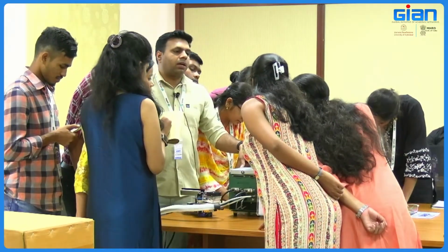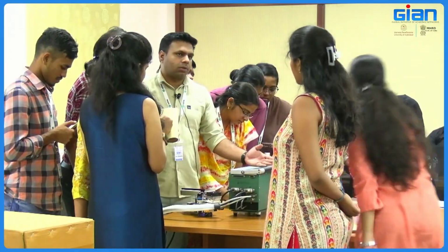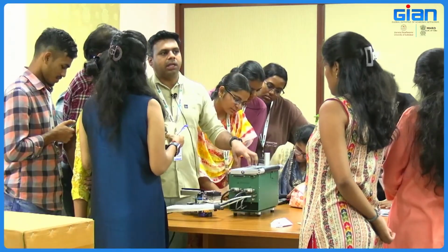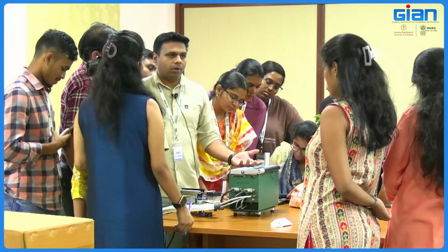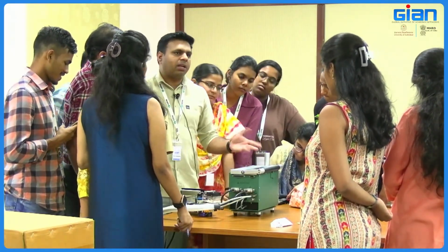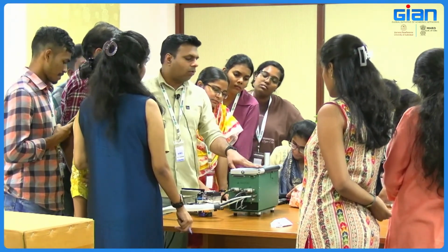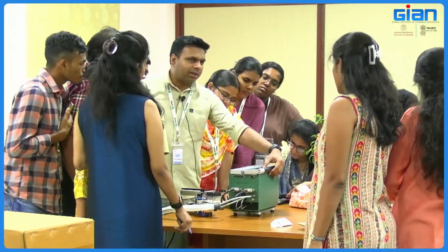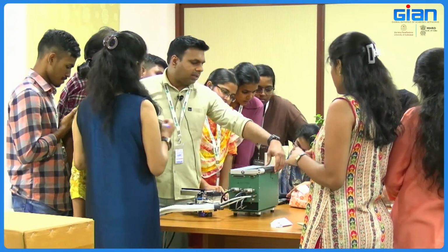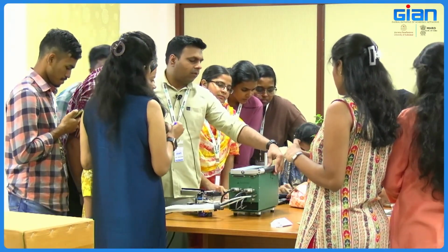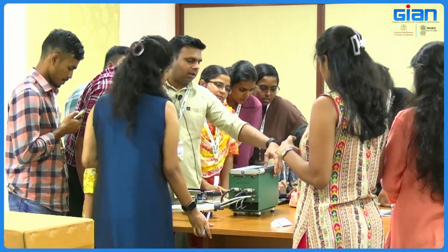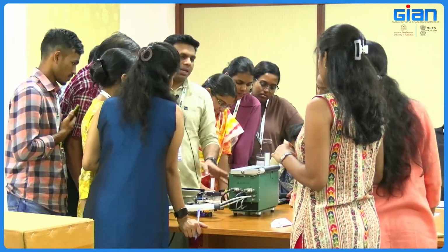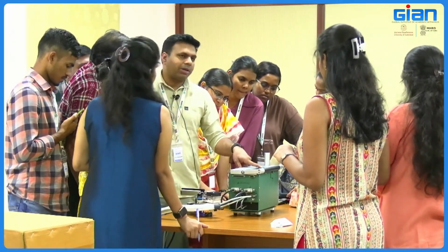Another thing is that before taking any readings, we have to match the CO2 reference with the CO2 sample. But before matching, we have to wait until the IRGAs warm up. It will take about 10 or 20 minutes to warm up. After this, you can do the matching. Then this is your water reference and this is your water sample, and this is your net change. What is the change between reference and sample? Here it is reflected. It should not be negative, but because we have not kept any leaf and this is not calibrated, it's showing negative.